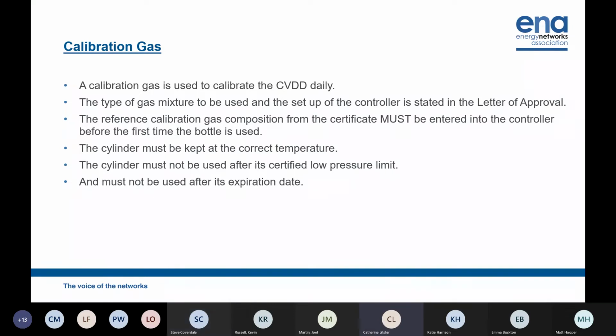So if your CV determination device fails to produce a valid CV in the gas day, so it's not working whilst you've been flowing, or if the calibration details aren't correct, or you haven't had a valid 35-day test in the last 35 days, that will create a loss of record. That loss of record means that your CV can't be used in the flow weighted average calculation, but something else has to go in there instead. It can't be left blank. So our main attribution would be that we'd use the lowest CV in the last year for your site. If your site hasn't been running for an entire year, then it will drop to a fallback value of 37 instead. And that's as detailed in the thermal energy regs. Yeah.